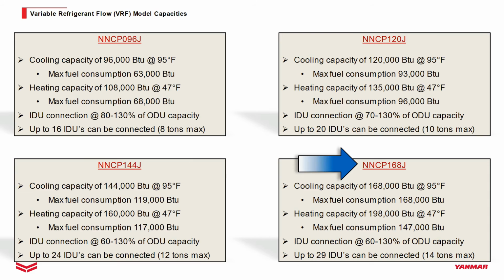Let's focus on the NNCP 168J specifications on the bottom right of this slide. The first bullet states a maximum cooling capacity of 168,000 BTUs, which coincides with the model number. Also, the maximum fuel consumption in cooling mode is the same at 168,000 BTUs. However, in heating mode, the heating capacity is 198,000 BTUs with a maximum fuel consumption of 147,000 BTU. This means the system can produce heat at a much greater volume than the amount of energy being consumed. The benefit to our customers is significant, with an important emphasis on energy conservation.